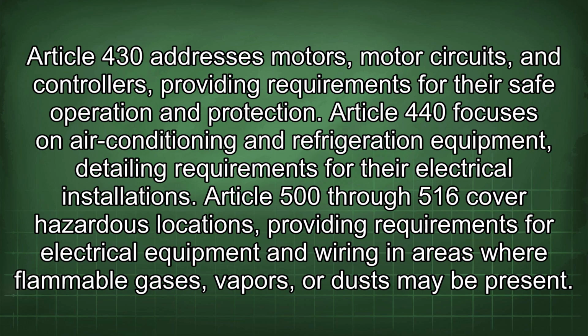Article 430 addresses motors, motor circuits, and controllers, providing requirements for their safe operation and protection. Article 440 focuses on air conditioning and refrigeration equipment, detailing requirements for their electrical installations. Articles 500 through 516 cover hazardous locations, providing requirements for electrical equipment and wiring in areas where flammable gases, vapors, or dust may be present.